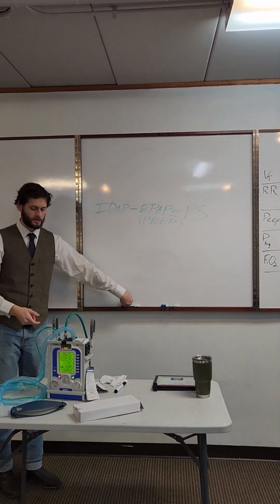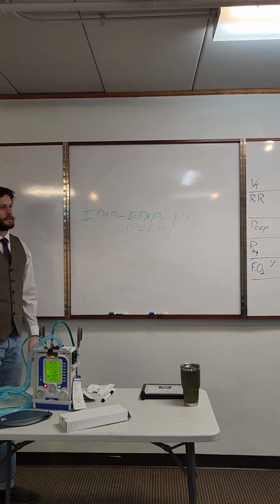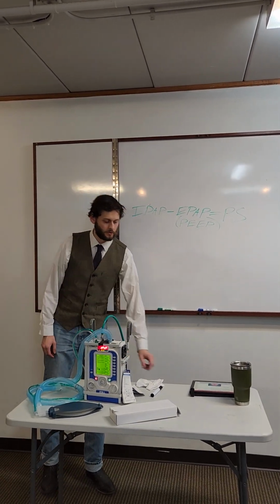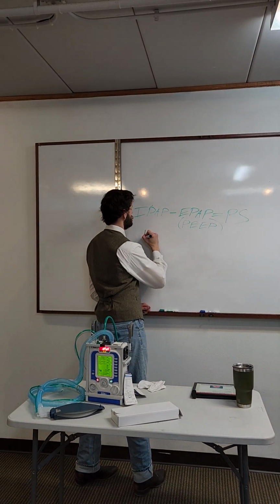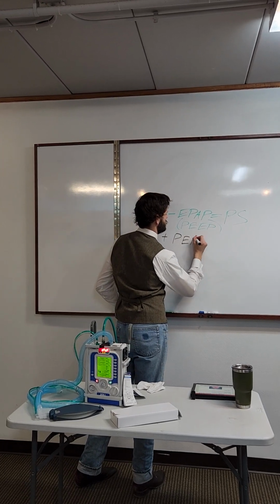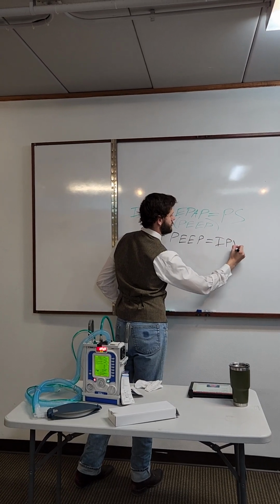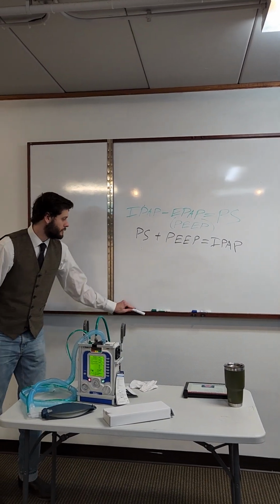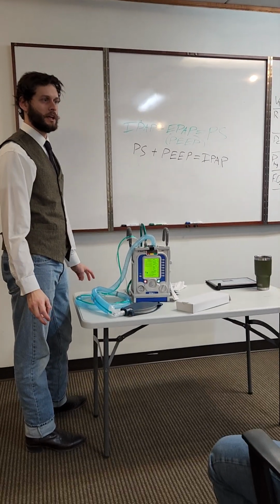So that's the one thing to keep in mind. In bi-level, we set these two settings. In the CPAP mode or the Newport mode, we set these two. So if we need to rearrange, all it is, pressure support plus PEEP is equal to the IPAP.